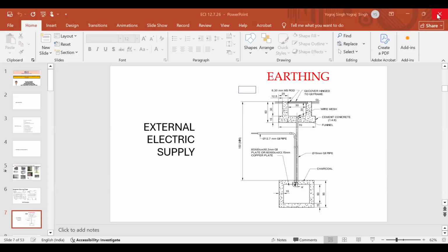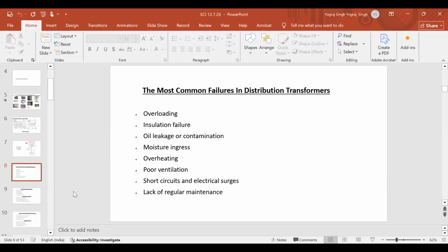Transformer failure happens because of overloading, insulation failure, oil leakage or contamination, moisture ingress, overheating, poor ventilation, short circuits, and electrical surges, lack of regular maintenance. Now overloading, आप बोलोगे ट्रांसफॉर्मर तो मैंने 500 kVA का लगाया हुआ है, but why is it overloading? My total load is less than 500 kVA, so I should say my transformer is not overloaded.